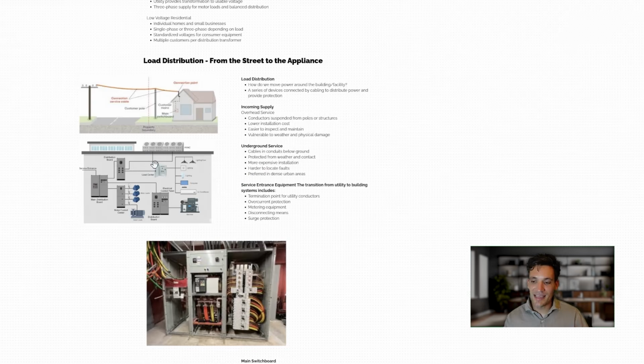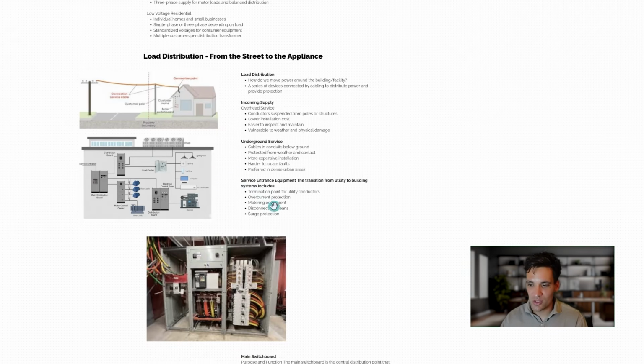This is where we connect the electricity distribution network. If we're working on a large piece of infrastructure like a tunnel, a data center, a hospital, we'll generally connect on the high voltage side and have our own internal transformer. But if we're working on a commercial building, residential, these sorts of things, we will have a low voltage connection. This connection can be an overhead service like most houses, where you have a wire coming directly off the residential transmission lines, or it can be an underground service where you have conduits running into your facility.